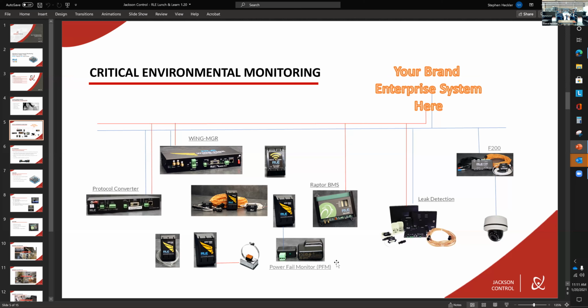But the end goal is ultimately to get a system that's delivering data value onto your existing MSTP or RTU network, which is what we're historically known for. There's documented well over 19 million installed feet of our sensing cable globally. Our leak detection is installed in all kinds of buildings all over the world, but again, we're built for mission critical. So all the data centers out there historically love our leak detection for a variety of reasons, which I'll touch on later. But we have a whole platform of different systems to be able to drive those outcomes.